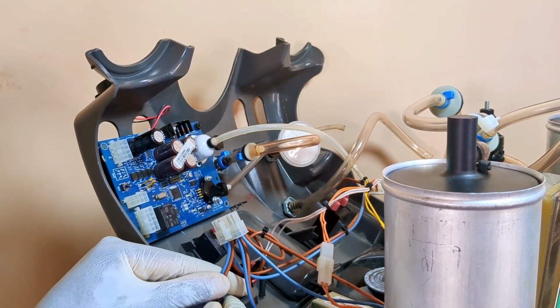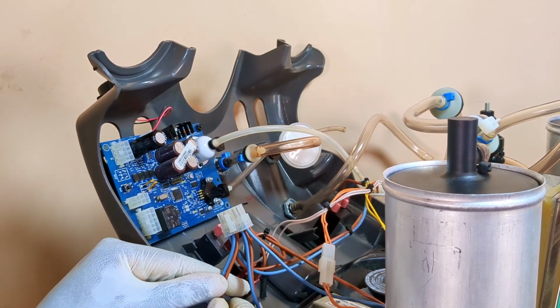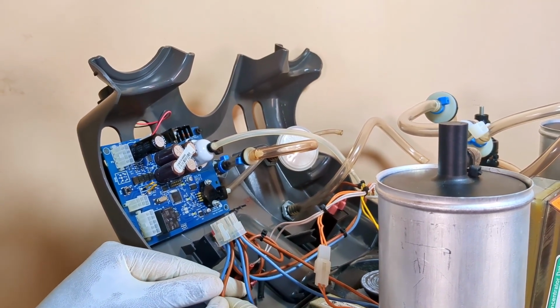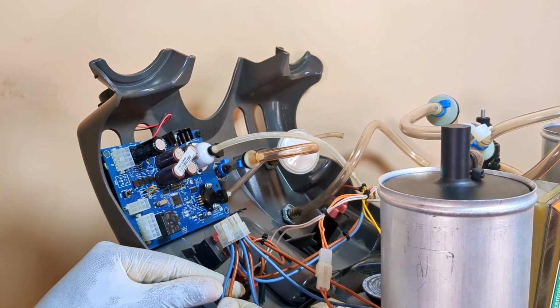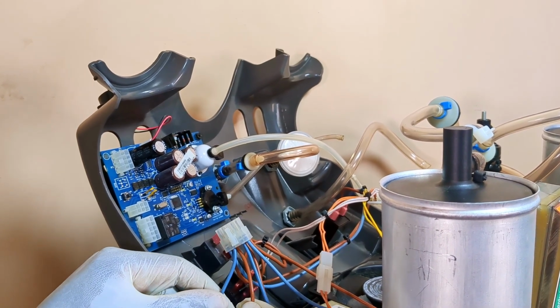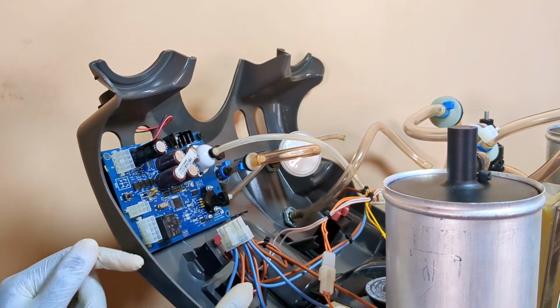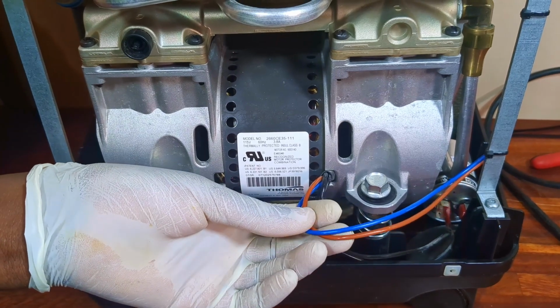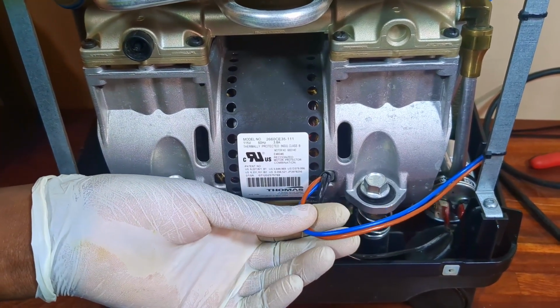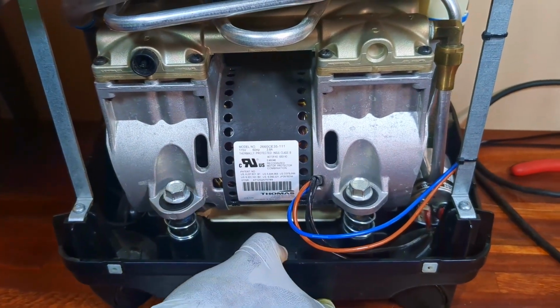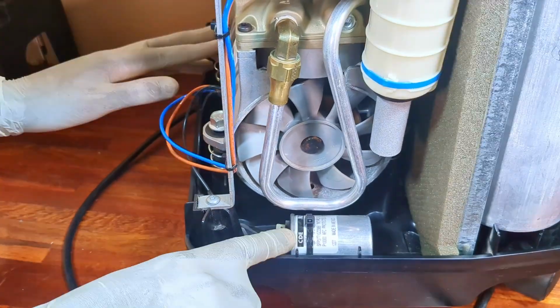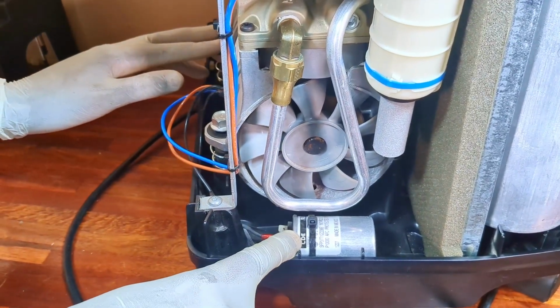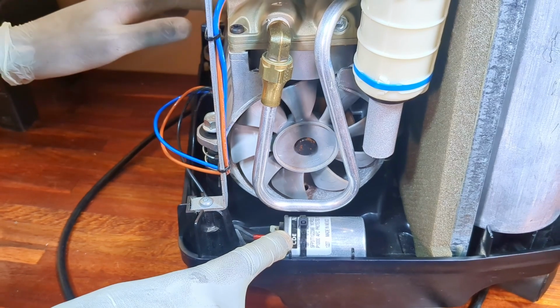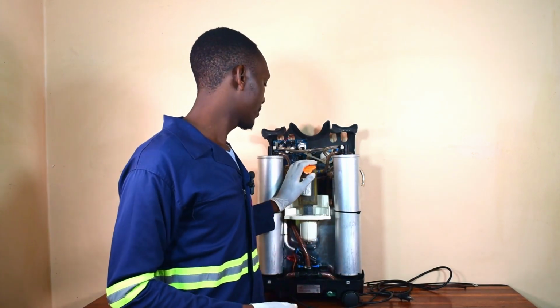The compressor is also connected in parallel with the power cables, hence it also receives 120 volts AC, with this brown being live and this blue being neutral. These are the cables that power the compressor. A starter capacitor is connected in series with compressor's stator winding. That's all on the electrical system of this oxygen concentrator.